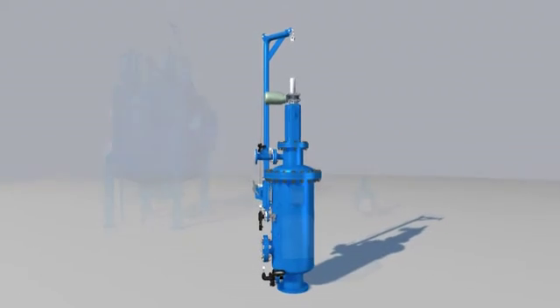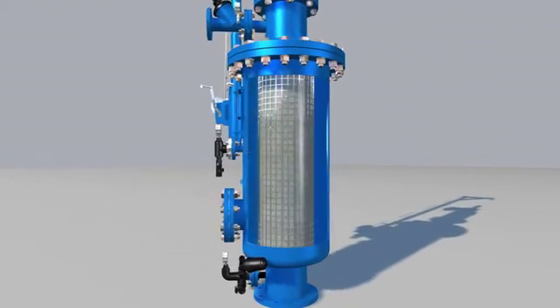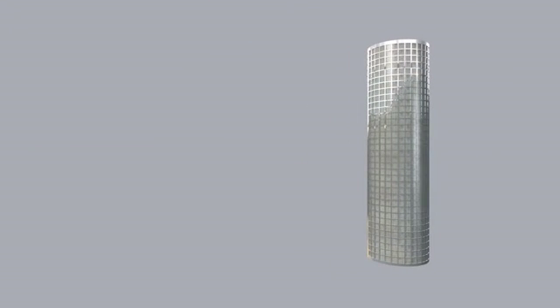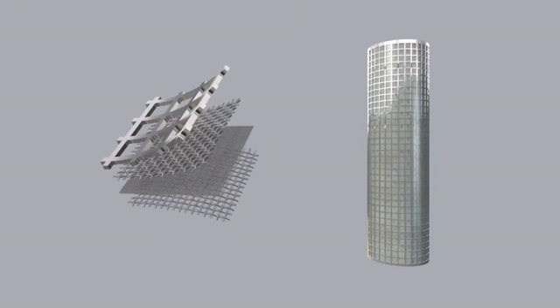These filters cover a wide range of flow rates between 5 cubic meters per hour and 5,000 cubic meters per hour, with filtration degrees from 10 to 2,000 microns, thanks to the wide variety of filtering screens.